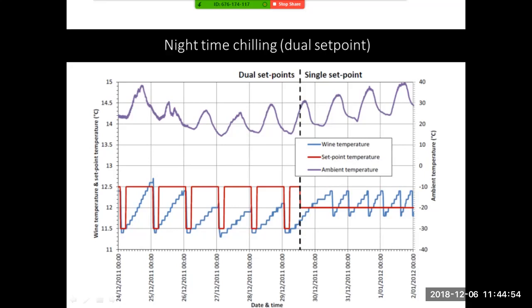So the Australian Wine Research Institute used a dual set point method instead. On the left-hand side, instead of a 12 degree temperature set point for the wine, at 1 a.m. they bring the temperature set point down by 0.5 degrees. This forces the refrigeration system to kick in and cool the wine down to 11.5, giving a couple of hours to do this. After 2 hours, the set point temperature then jumps back up by a degree to 12.5.